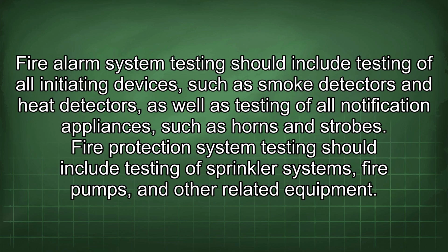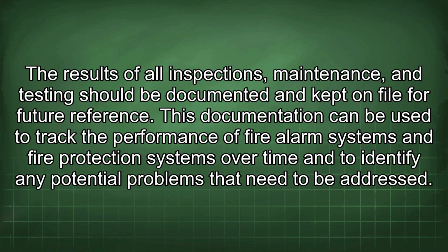Fire alarm system testing should include testing of all initiating devices, such as smoke detectors and heat detectors, as well as testing of all notification appliances, such as horns and strobes. Fire protection system testing should include testing of sprinkler systems, fire pumps, and other related equipment. The results of all inspections, maintenance, and testing should be documented and kept on file for future reference. This documentation can be used to track the performance of fire alarm systems and fire protection systems over time and to identify any potential problems that need to be addressed.